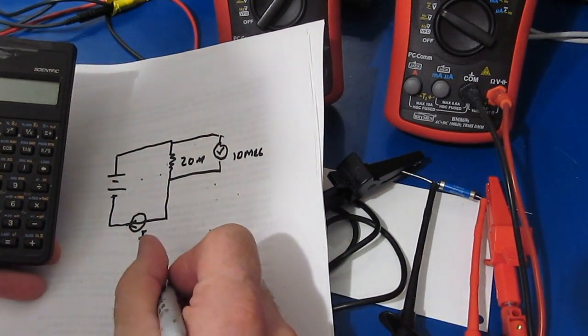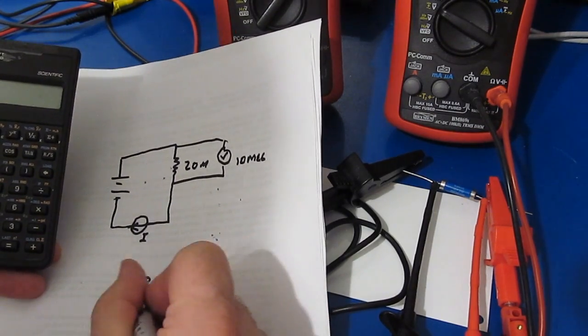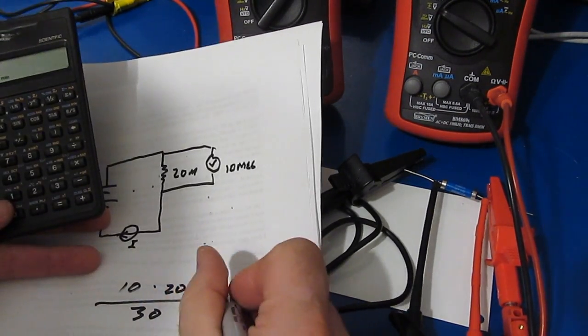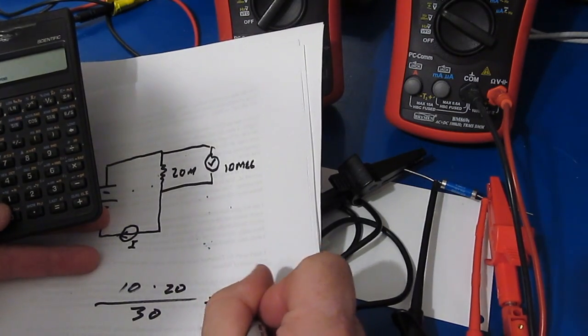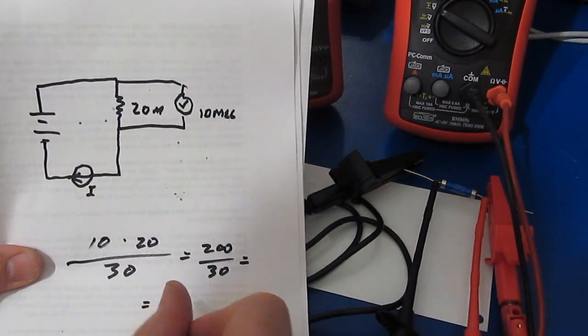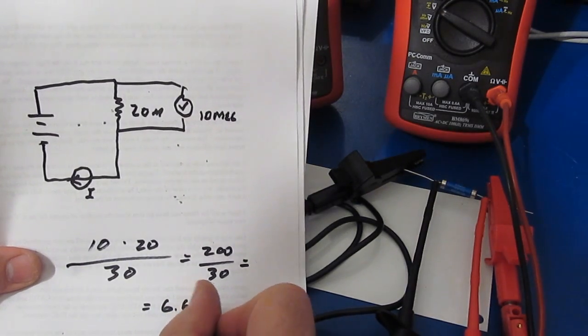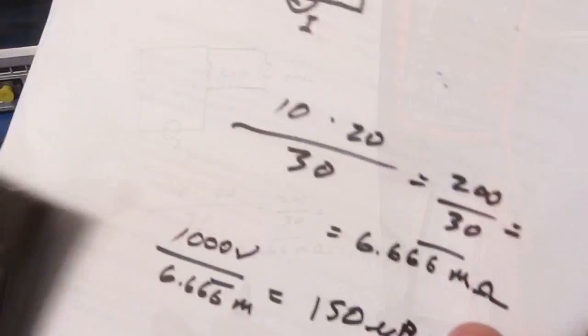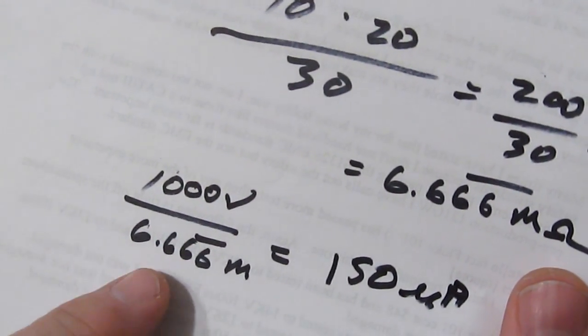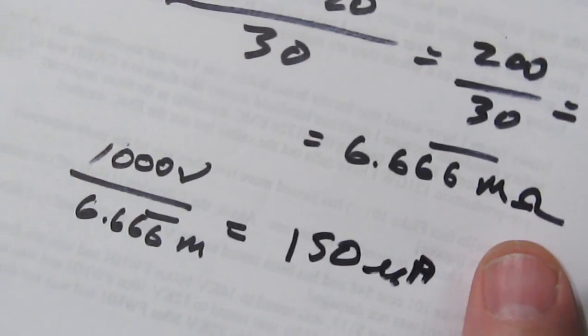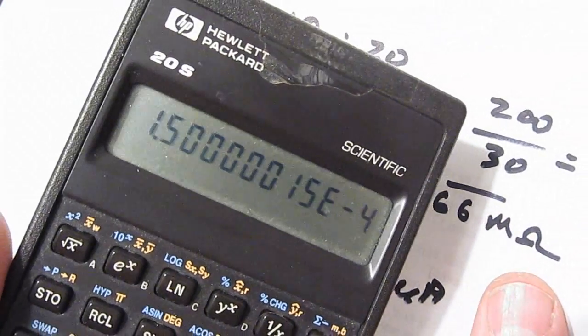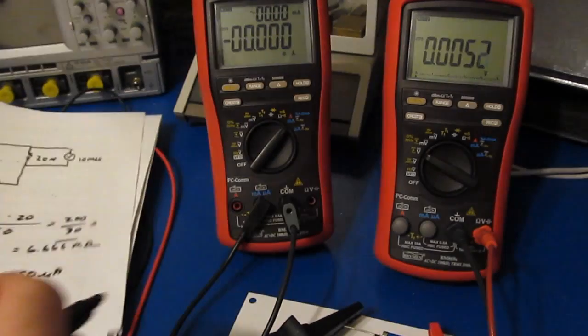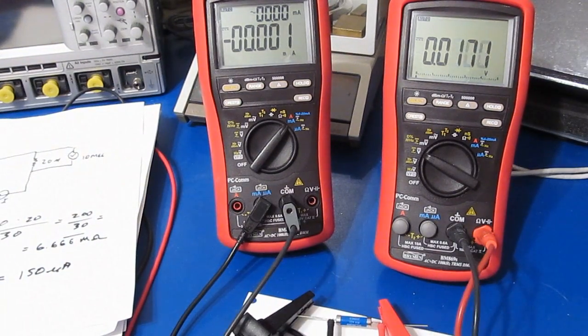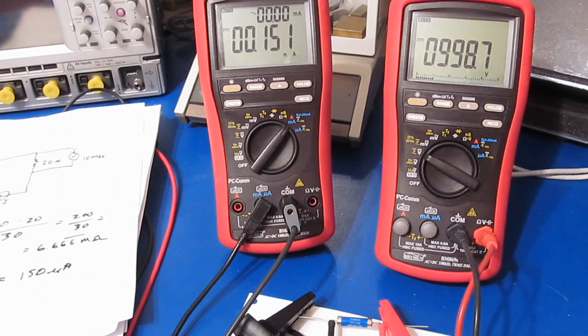So it's 10 times 20 over 30, or 200 over 30, equal to 6.666 mega ohms. If we take our 1000 volts and divide by 6.666 mega ohms, that's 150 microamps. Again, if we re-engage this, you can see it's exactly what we're reading, 150 microamps.